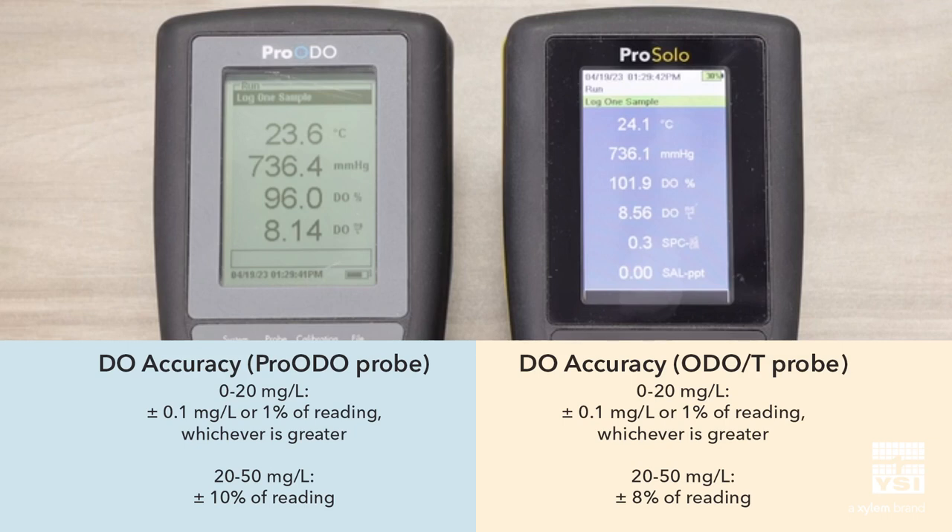As mentioned previously, the ProSolo uses the same sensing technology, resulting in comparable measurements to the ProODO. We've also been able to improve the accuracy in high dissolved oxygen environments.